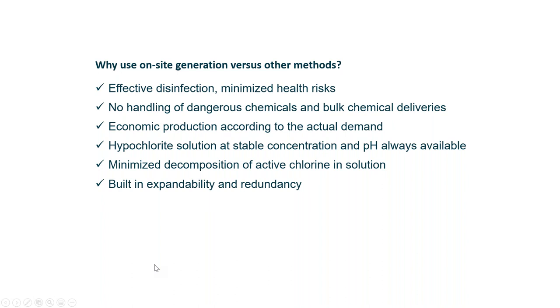The effectiveness of disinfection by using sodium hypochlorite generated on site is actually the same as using the bulk sodium hypochlorite that we get from suppliers that produce it. The reason is we can assure that any desired ppm can be reached in the water. The second one is no handling of dangerous chemicals and bulk chemical deliveries. Our process requires only brine, electricity and water supply, making it safe, reducing risk to workers and environment compared to handling gas chlorine cylinders and high concentration sodium hypochlorite. Furthermore, low concentration sodium hypochlorite is generated through this system, making it safe to handle as well.